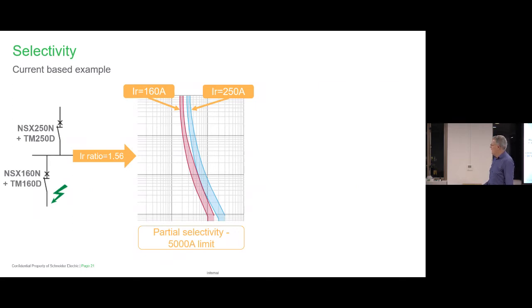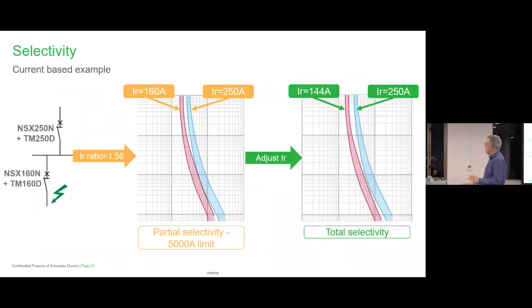Well, 5 kA sitting here on a 160 on a main board, you might find that's not great, not good. So we need to do something about that. We need to make some adjustment. We need to make some adjustment here, or we need to make some adjustment here. So the first thing, the most economical solution, if it is possible, is just lower this. And we end up with total selectivity. You can see how the curves have just come apart here, and now we have it. But you might not be able to do this.